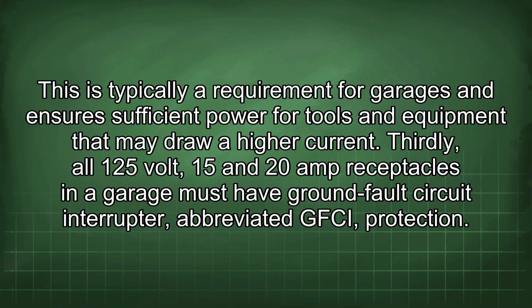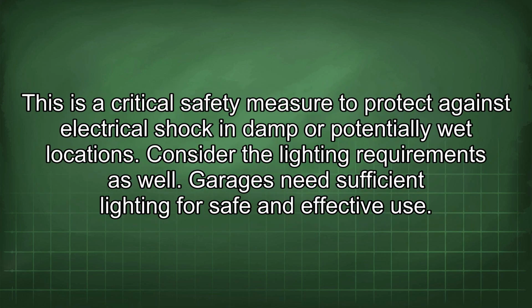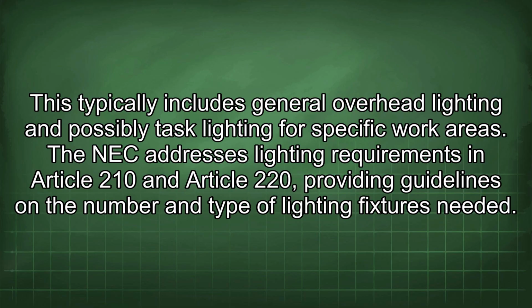Thirdly, all 125-volt, 15 and 20-amp receptacles in the garage must have ground fault circuit interrupter, abbreviated GFCI, protection. This is a critical safety measure to protect against electrical shock in damp or potentially wet locations. Consider the lighting requirements as well. Garages need sufficient lighting for safe and effective use. This typically includes general overhead lighting and possibly task lighting for specific work areas. The NEC addresses lighting requirements in Article 210 and Article 220, providing guidelines on the number and type of lighting fixtures needed.